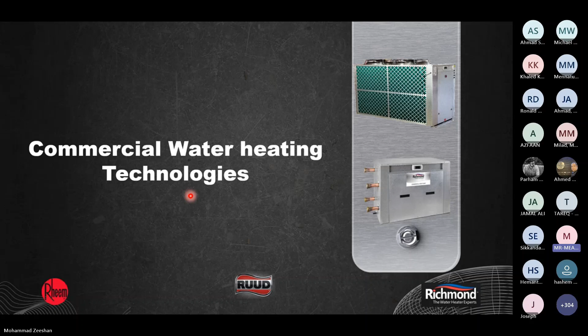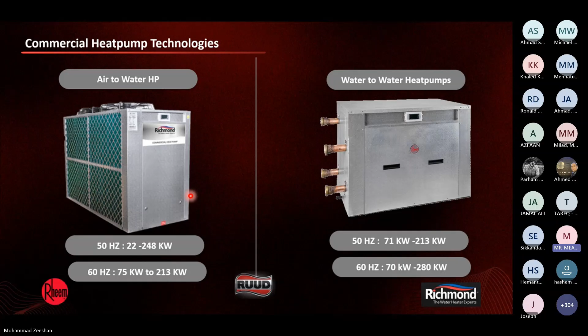Let's go to commercial water heaters. This is the second part of our presentation. There are two types of commercial heat pump technologies currently available. In the previous slides, in the residential segment, there are only air to water heat pumps. The energy is taken from the air and transferred to the water, which is why they are air to water heat pumps. In commercial, you also have water to water heat pumps, which take energy from the water on one side and transfer that to the water on the other side.